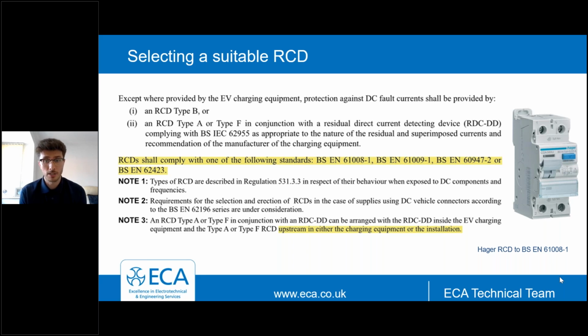So if it's a proper dedicated RCD, a bit like the one shown on screen here, and that's within the device, that could be perfectly fine, providing it meets those standards. However, often devices that are built within EV charge point equipment are integrated into printed circuit boards, known as PCB devices. And these may not fully conform to the standards listed on screen, for example, BS EN 61008. And what we sometimes find with this, sometimes the manufacturer may make statements such as they are PCB compliant to BS EN 61008. And this then leaves the installer in a bit of a tricky position, because it seems that they may be partially compliant and they may meet elements of the standards.